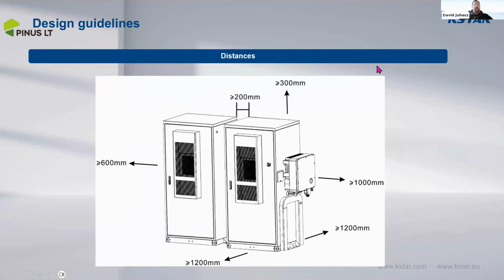And we have the minimum distances for planning the system. This is 1.2 meters from the bottom and the front. And from the right, we need to keep 1000 millimeters for handling the inverter and checking the indicators there. And on the top, if we want a roof, we need to keep a 300 millimeter distance.